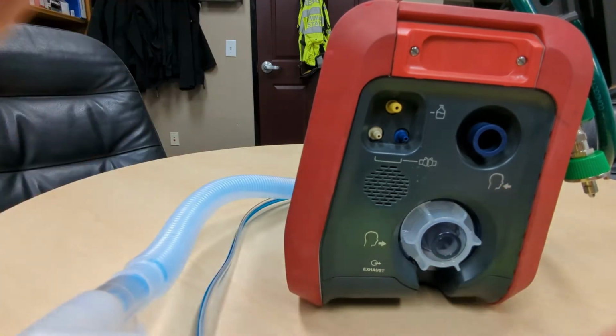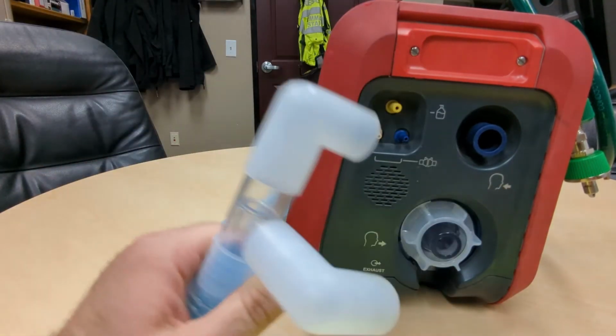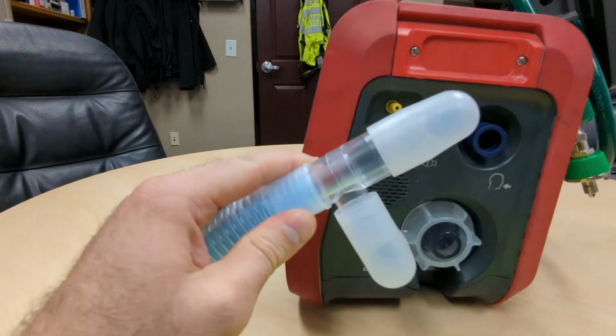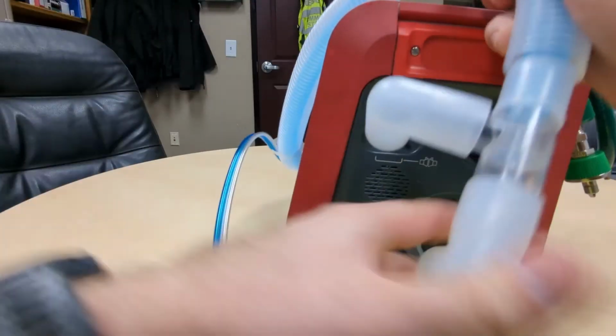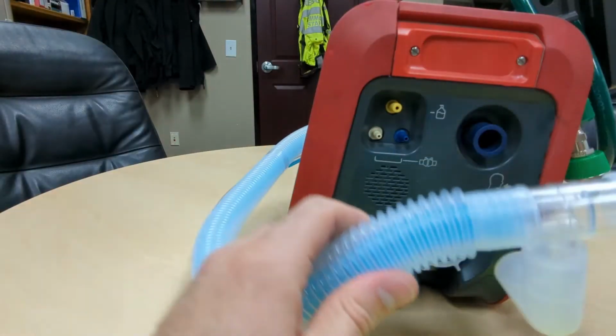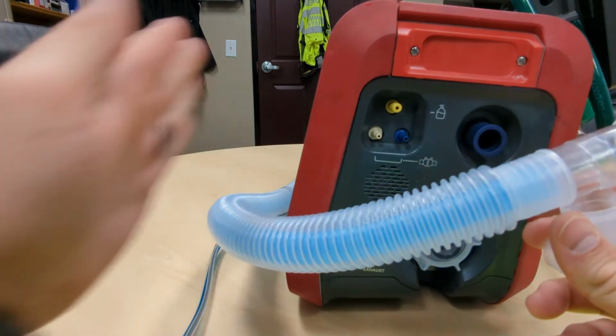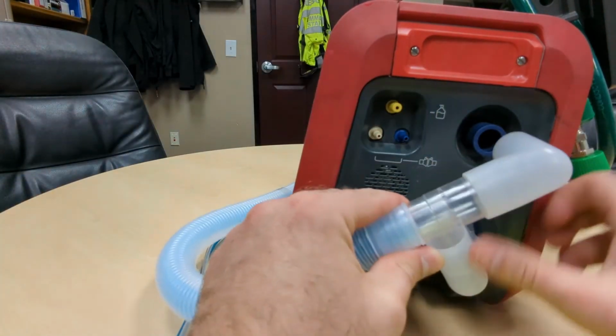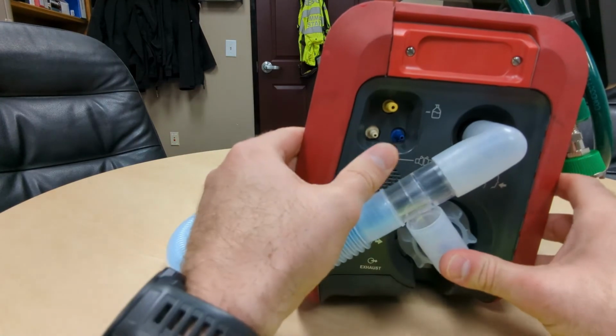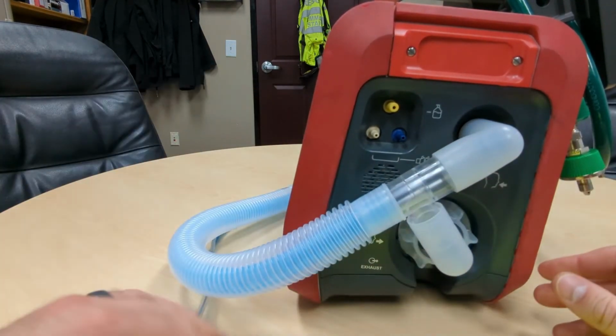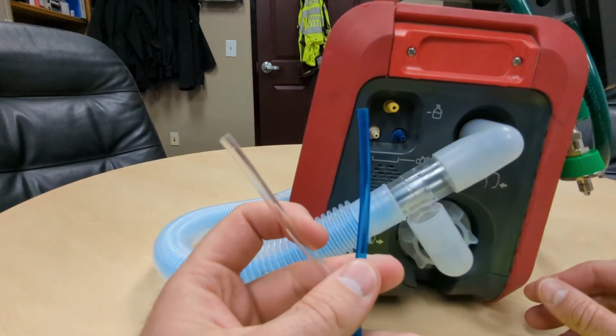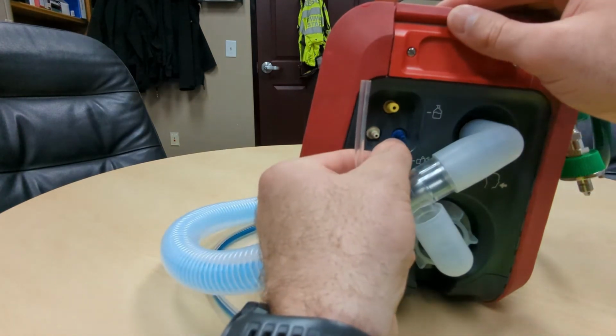You'll feel it. Next, for the main circuit, make sure it's pointing forward. It will install backwards like this. So always make sure that the output is coming forward towards the front of the ventilator. These are just press-on fittings. And then lastly, the flow sensor lines. They're color-coded, and it's just press fit.